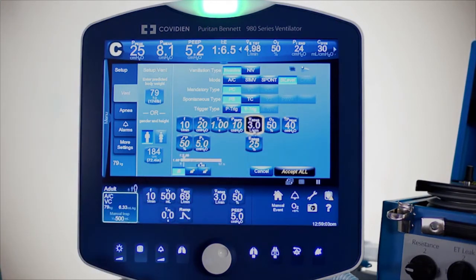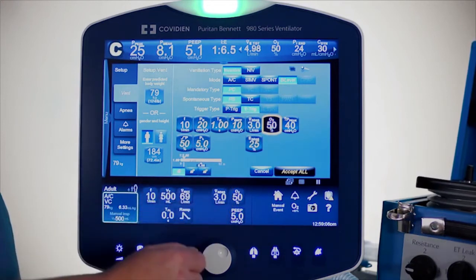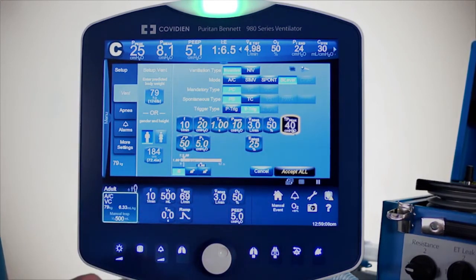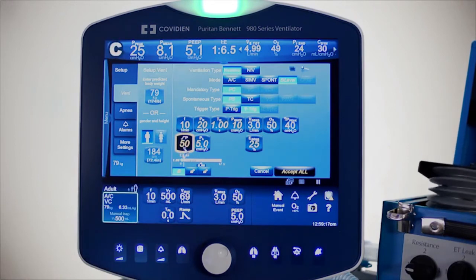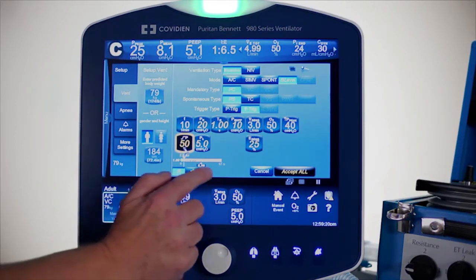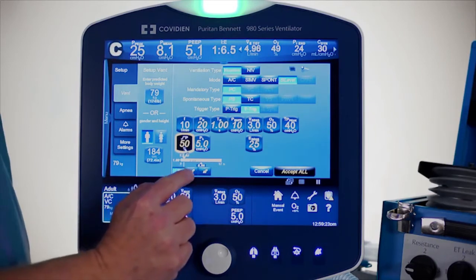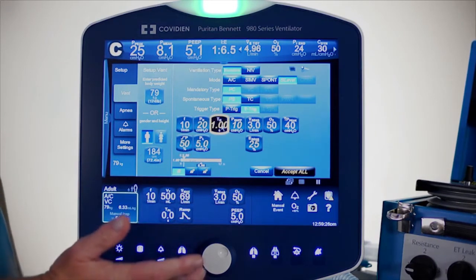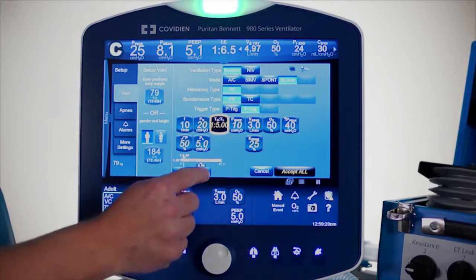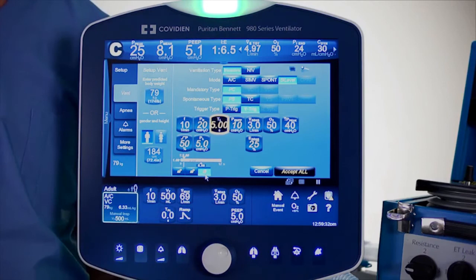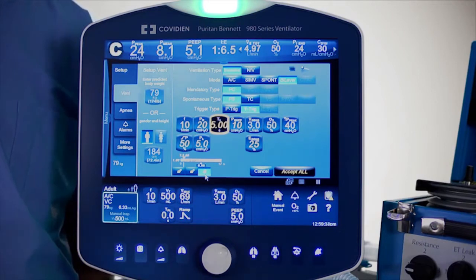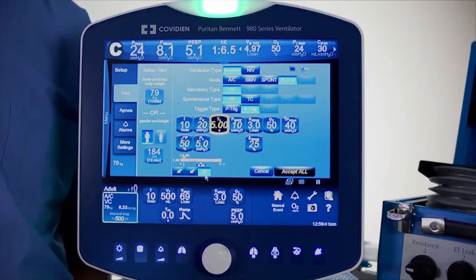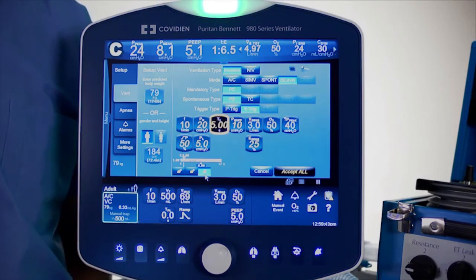Next are the traditional settings: flow sensitivity, O2 percentage, high pressure limit, and expiratory sensitivity — related to pressure support use. It is a pressure control, so there is a rise time. Down below you have locks. The question is: what is the most important variable you want to set — the inspiratory time, the I:E ratio, or the release time? When doing the APRV approach, you may want to lock the expiratory time or release time as the primary variable, but first I'll start with inspiratory time locked.